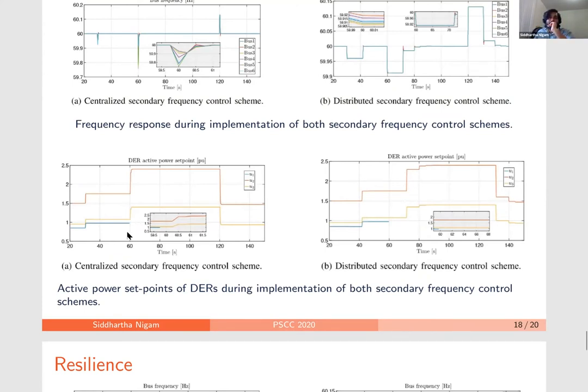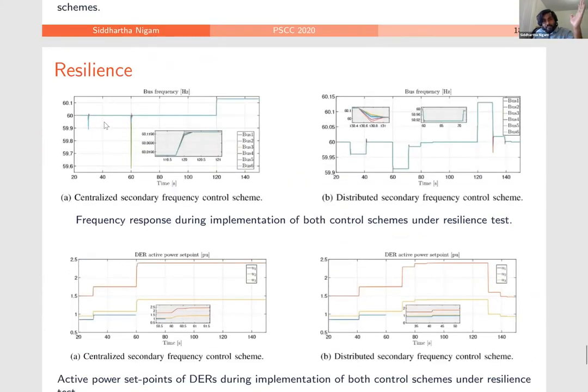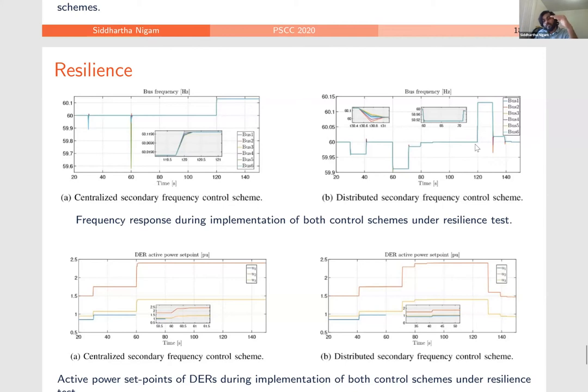At the 60-second mark, as mentioned, the microgrid loses an inverter, so the control nodes don't have information for that. These are the setpoint updates for the centralized scheme and the distributed scheme. For resiliency testing, the profile is the same, but the CompactRIO device is unplugged at 80 seconds, so after that any perturbation cannot be corrected by the centralized node. In the distributed setting, a node is removed at 80 seconds and another at 100 seconds, and when the perturbation happens at 120 seconds — losing a load — it takes more time, but the system is able to bring the frequency back to 60 Hz because of the failure-adaptive protocol.